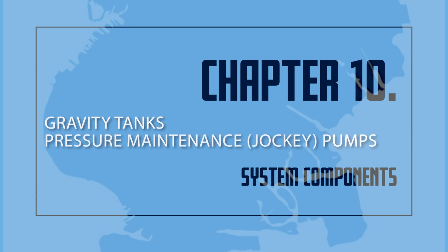Pressure maintenance pumps or jockey pumps. Pressure maintenance pumps, sometimes referred to as jockey or makeup pumps, are often found on sprinkler systems. These pumps are designed to automatically operate when there is a slight drop in pressure due to the leakage in the system or a pressure surge. The jockey pump restores the pressure in the fire protection system to the desired level. When the drop of pressure in the system is greater than the capacity of the jockey pump, the fire pump is activated.